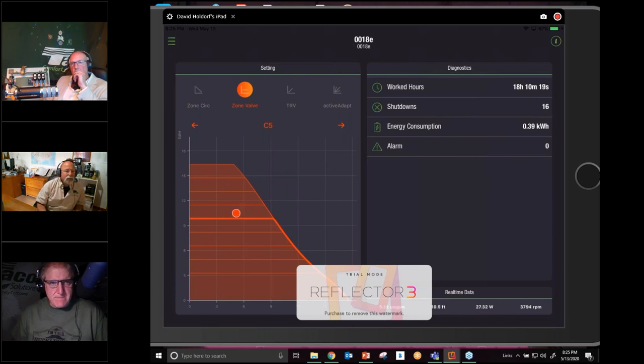So what it's going to do now is, as you start closing the zone valves manually, you're going to see that thing go left to right. And again, that's a midnight, no time to do anything, need to get the pump in there, but I want to get it in the right mode of operation. I'm just getting a sense of what the resistance of the system is at full blast. And the reason I'm saying this is, how many times do we need everything that system's got to offer? Most systems are oversized. That's why I'm saying it's better to go underneath. You'll get more movement from left to right the farther down you go with that.